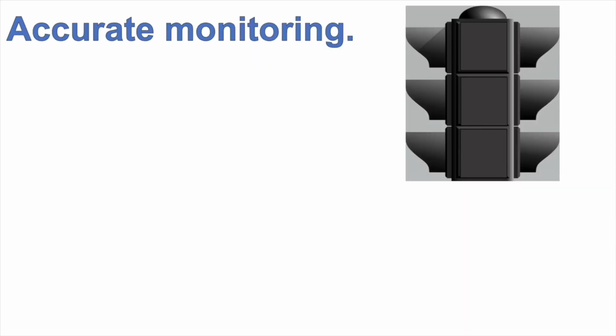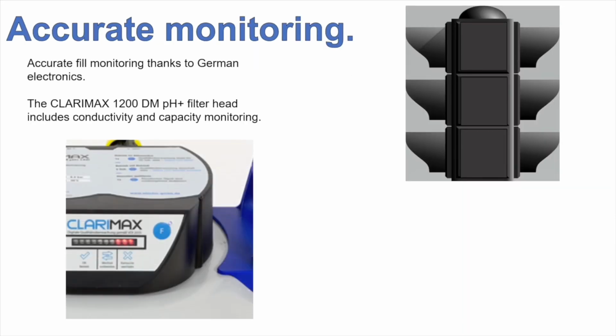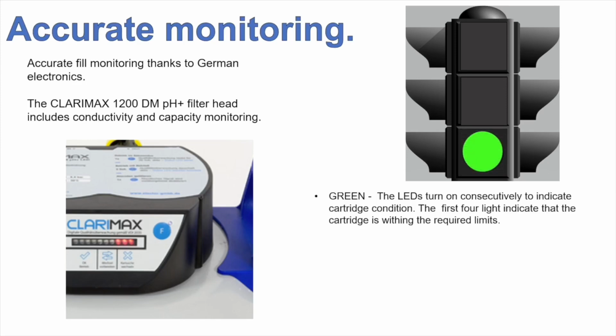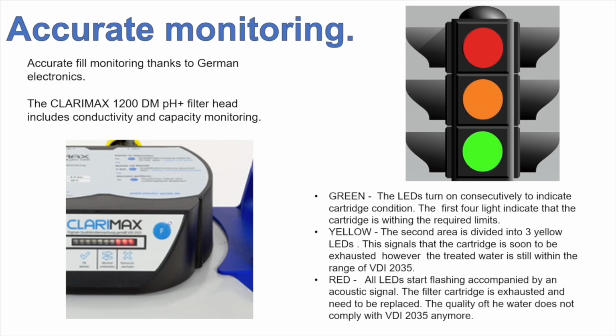We've got accurate monitoring using the Clarimax. It's German engineering, it's German electronics, it works really, really well, it's really, really accurate, and it's easy to follow. We have the traffic light system, so we've got green, yellow and red. Green means we're within the limits we want. Orange, the resin's starting to expire. Red, we're no longer within the VDI requirements anymore, so we need to change our cartridge.